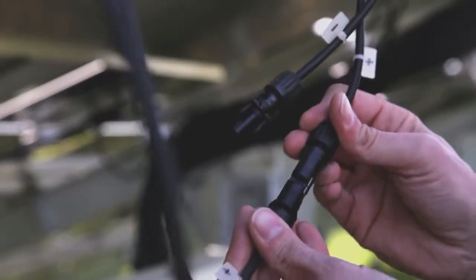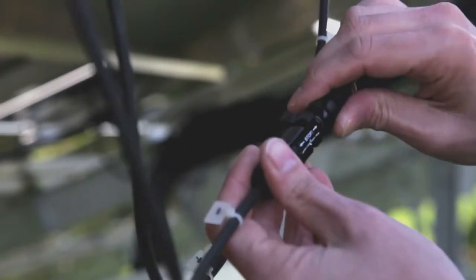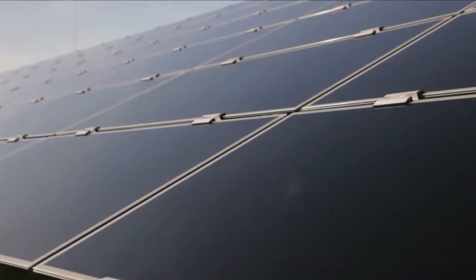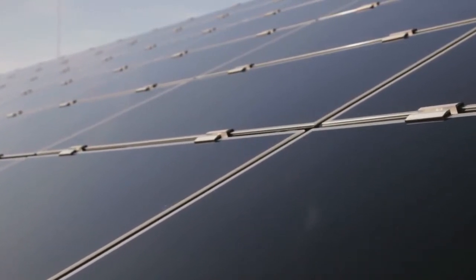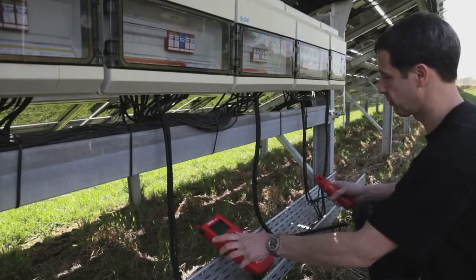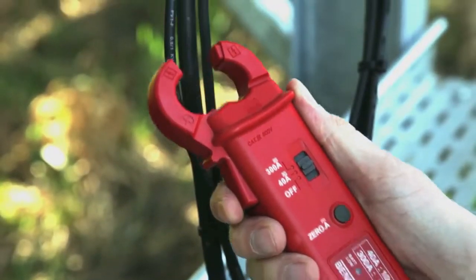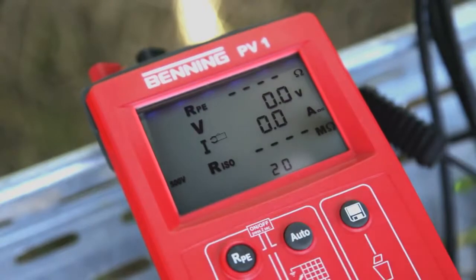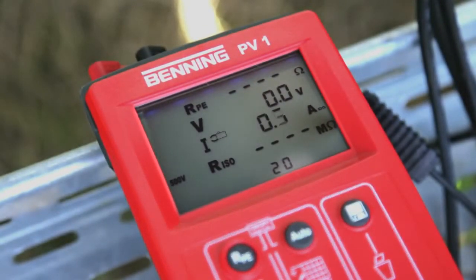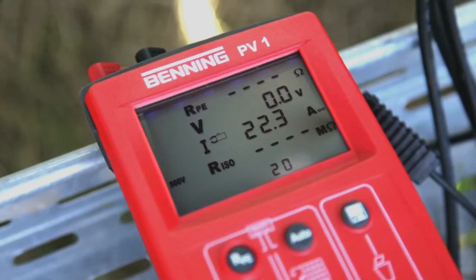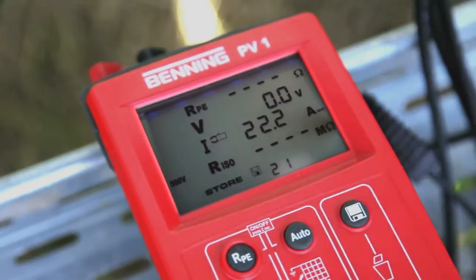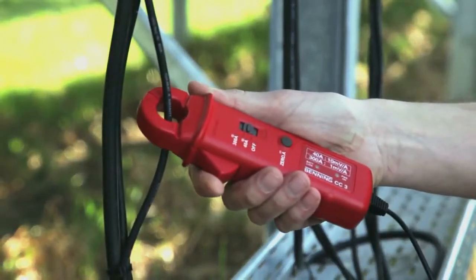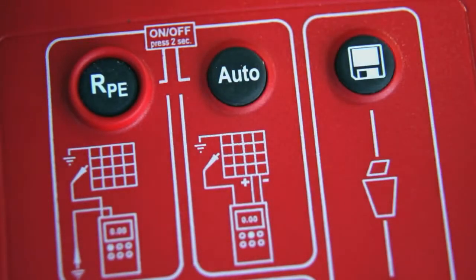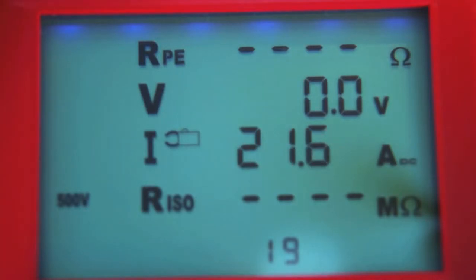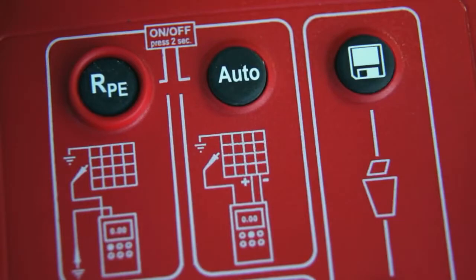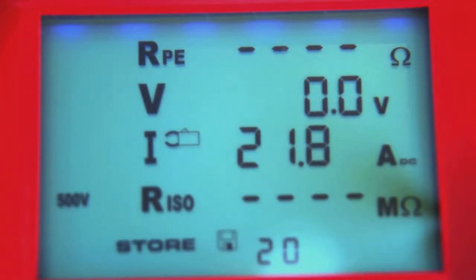For a concluding performance test of the individual PV strings, reconnect the strings to the inverter. Connect the Benning CC3 current measuring clamp to the PV1 and compare the actual performance of the individual PV strings. Under identical insolation conditions, the performance of the PV generators should deviate not more than 5% from each other. Store the individual measured values in the device and conveniently compare them by means of the Recall function.